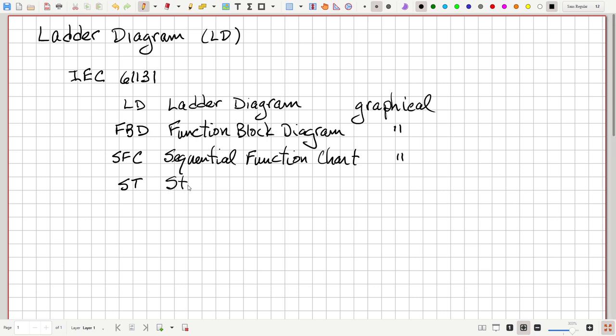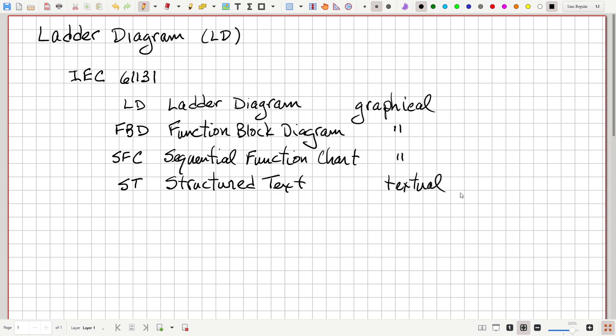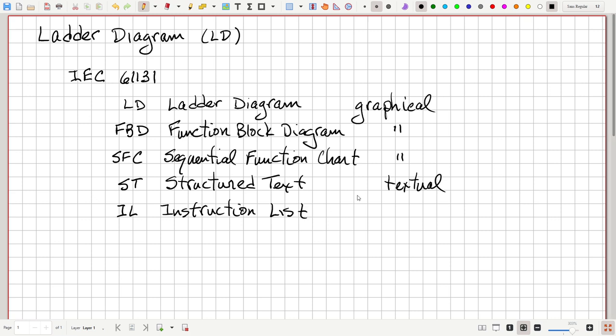Then there is ST, which is structured text — it is a textual language. And then the fifth one is IL, which is instruction list. It is also textual, but it is deprecated, meaning its use is frowned upon or discouraged. It is a cryptic language that looks a lot like a CPU's instruction set assembly language. We have to be aware of it because there is some old code written in instruction list, but for new projects we would want to only make use of the first four of these languages.